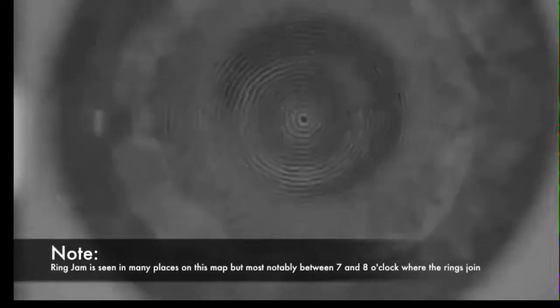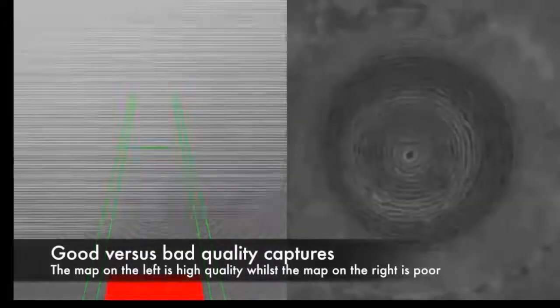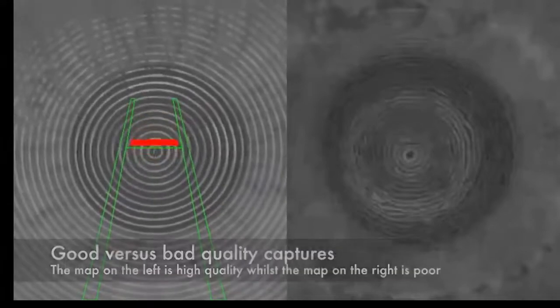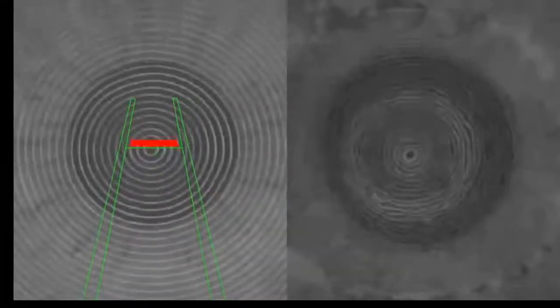However, in the second example, we see the mires are not intact, and the Placido disc image shows ring jam. Both of these captures showed an accuracy in the top right hand corner of 99%, yet the former will yield better quality data.